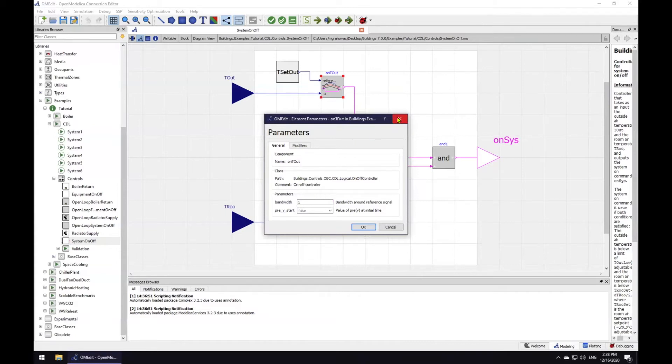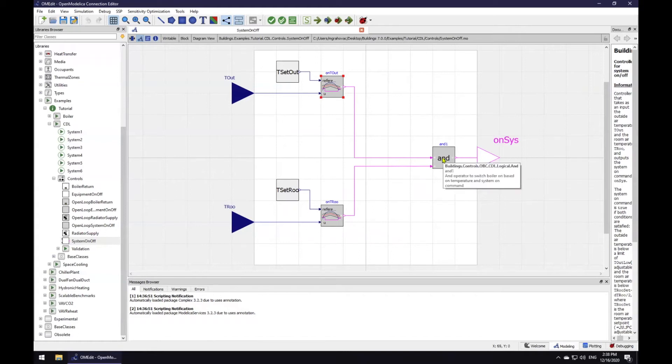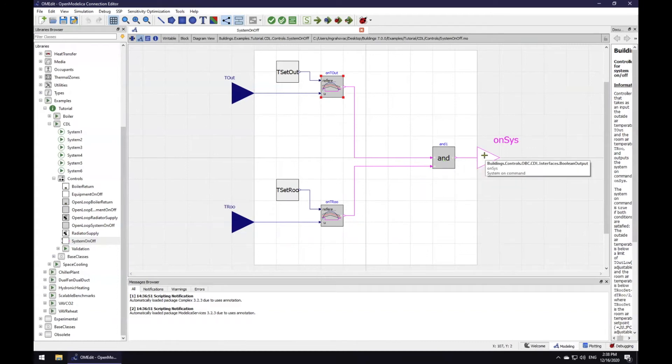In this small controller sequence, we would like the heater to only switch on if it was sufficiently cold outside and at the same time the room temperature is below its set point. In CDL, this is stated with this AND block. An output interface to send the output to a controlled device is on the far right of this block diagram.